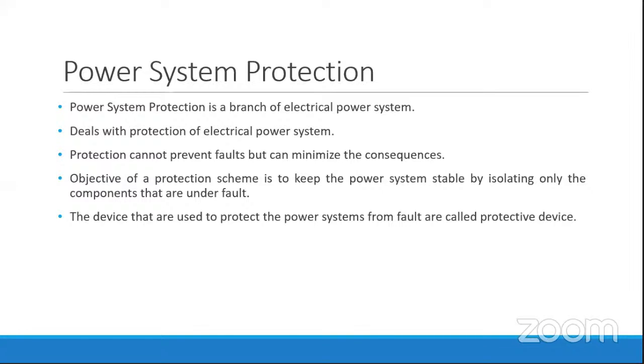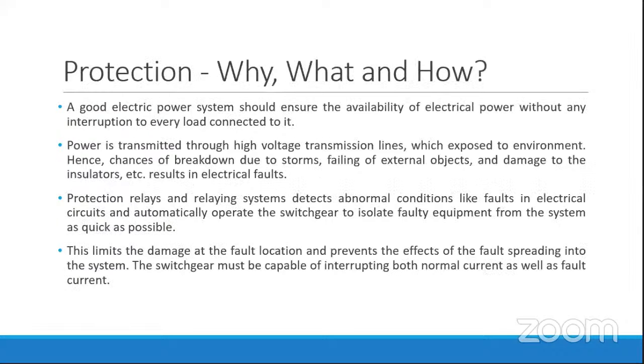In order to isolate a fault or to protect the equipment, the devices used to protect the power system from faults are known as protective devices. Protective devices include circuit breakers, relays, isolators, insulators, lightning arresters, etc. The terminology we use for these devices is switchgear. Moving ahead: protection, why, what, and how we need to protect this equipment.